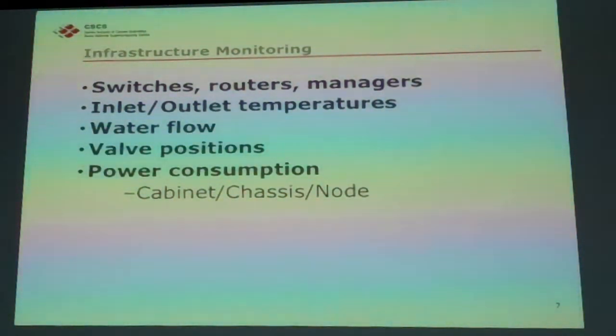Inlet and outlet temperatures. Computers are getting bigger, faster, and hotter. So a lot of liquid cooling is now moving back into computer centers. Monitoring the temperature of the water going into your cabinets and coming out of the cabinets, you can compute the differential. You can see if there's a problem. If your outlet temperature is suddenly rising, you might want to look at what's going on. Do you have a problem with water flow? Are you not delivering enough water at the right temperature to your cabinet?